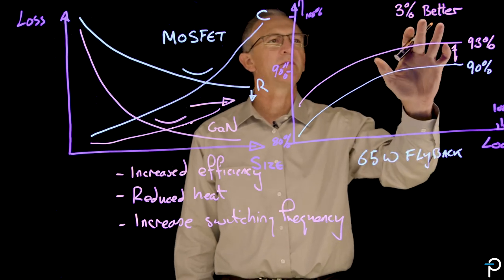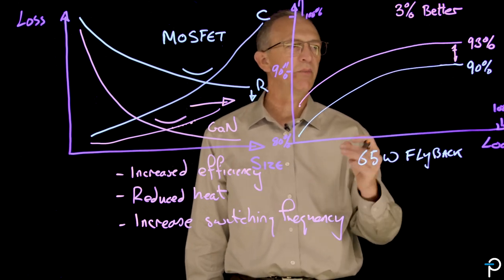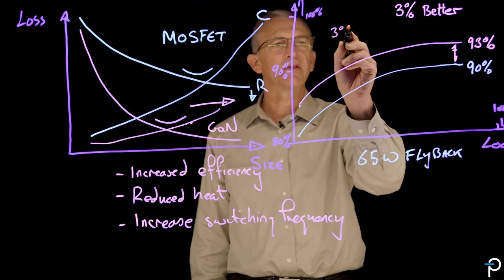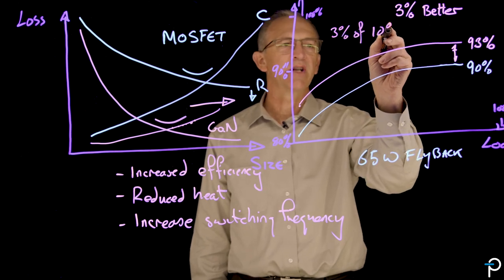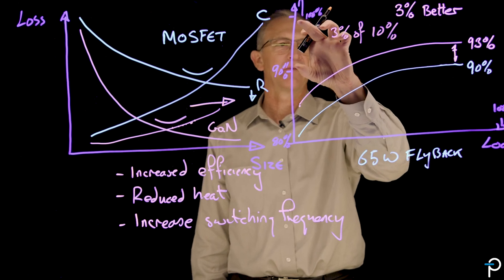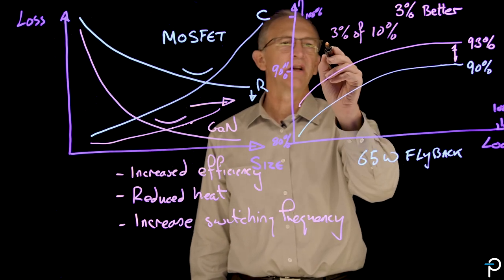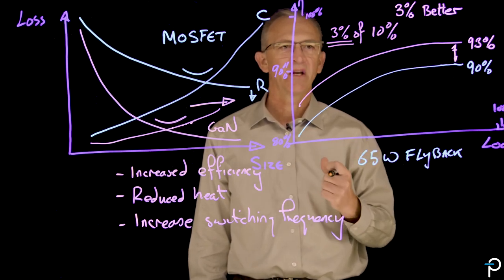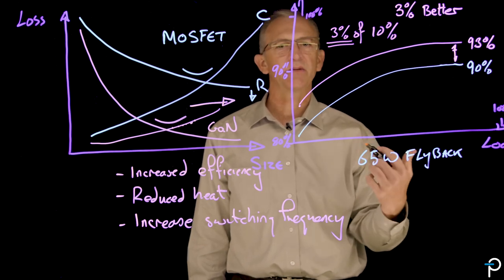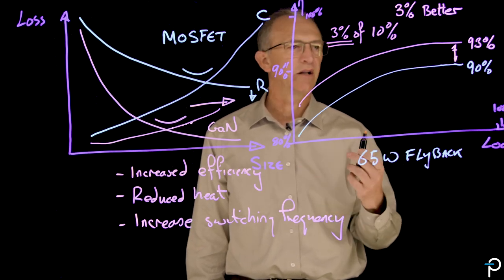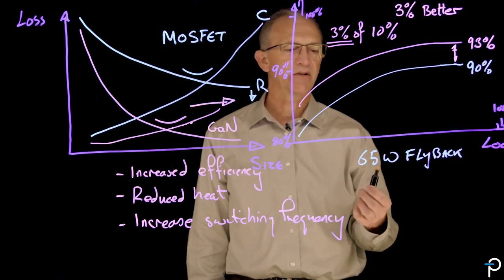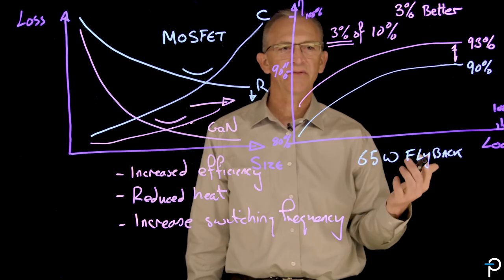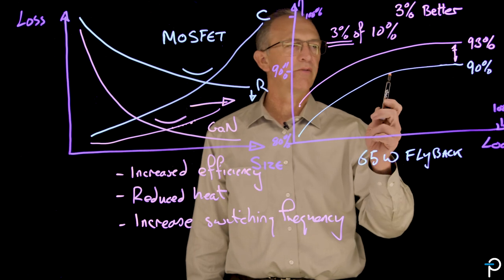Now, 3% doesn't seem like a lot. 3% is a relatively small number. But when you set it against where we are on the curve, what you'll notice is it's 3% of 10%, which are the losses for the power supply. So you're saving 30% of the losses that you would otherwise be generating in your power supply. That's 30% energy saved. That's 30% less energy you have to dissipate in your power supply. Less heat sinking, less size, longer lifetime, doesn't get so hot. So there are a variety of benefits.